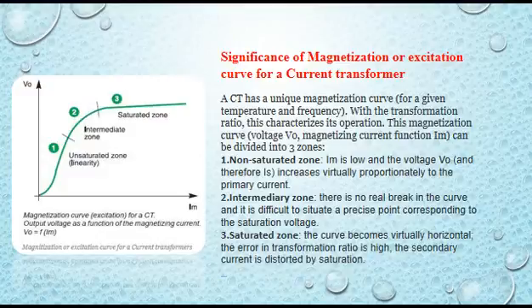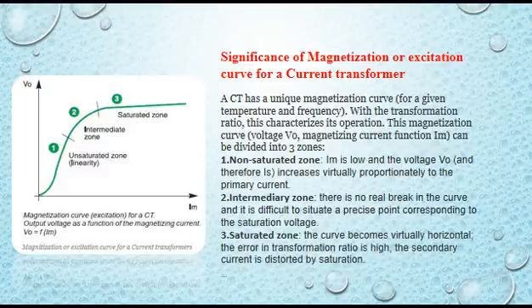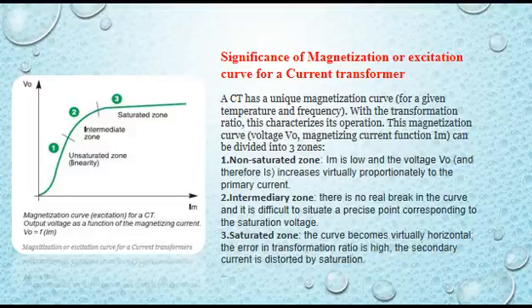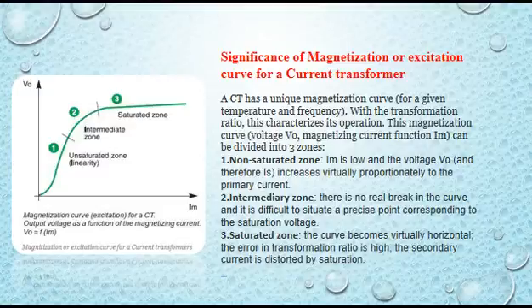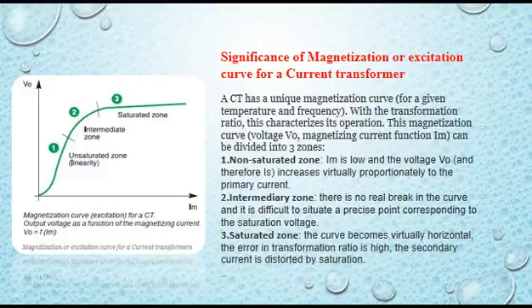In the non-saturated zone, Im is low and voltage and current increase virtually proportionally to the primary current — this is the linear region marked as zone one on the curve. In the intermediary zone, there is no real break in the curve and it is difficult to locate a precise point corresponding to the saturation voltage. In the saturated zone, the curve becomes virtually horizontal, the transformation ratio error is very high, and the secondary current is distorted by saturation.